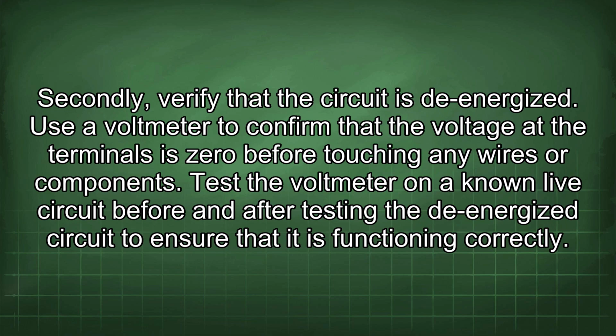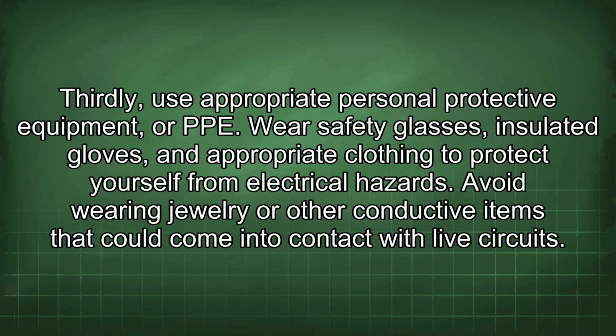Secondly, verify that the circuit is de-energized. Use a voltmeter to confirm that the voltage at the terminals is zero before touching any wires or components. Test the voltmeter on a known live circuit before and after testing the de-energized circuit to ensure that it is functioning correctly. Thirdly, use appropriate personal protective equipment, or PPE. Wear safety glasses, insulated gloves, and appropriate clothing to protect yourself from electrical hazards. Avoid wearing jewelry or other conductive items that could come into contact with live circuits.